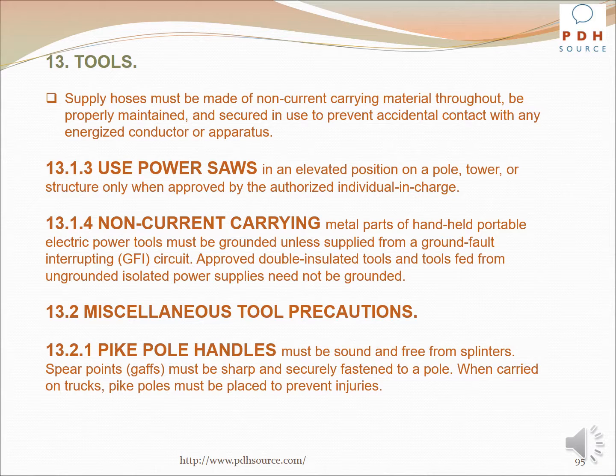Use power saws in an elevated position on a pole, tower, or structure only when approved by the authorized individual in charge. Non-current carrying metal parts of handheld portable electric power tools must be grounded unless supplied from a ground fault interrupting circuit, GFI. Approved double insulated tools and tools fed from ungrounded isolated power supplies need not be grounded.